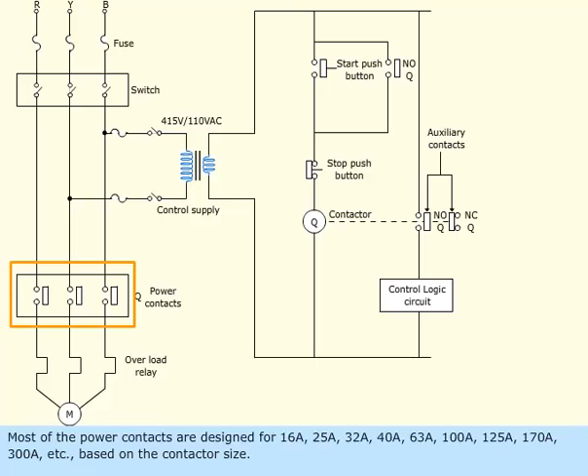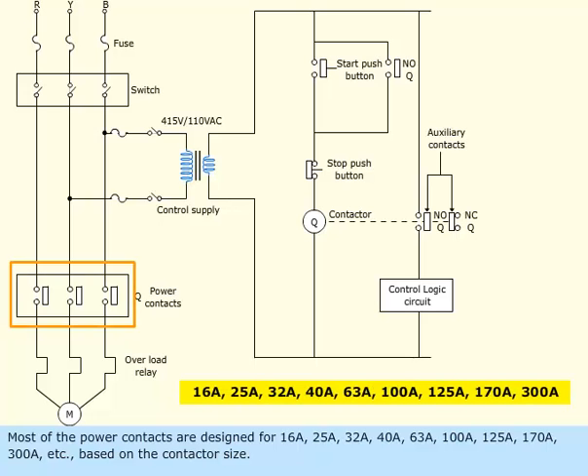Most of the power contacts are designed for 16A, 25A, 32A, 40A, 63A, 100A, 125A, 170A, 300A, etc., based on the contactor size.